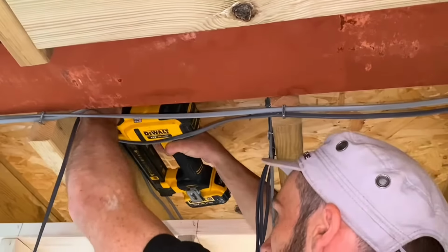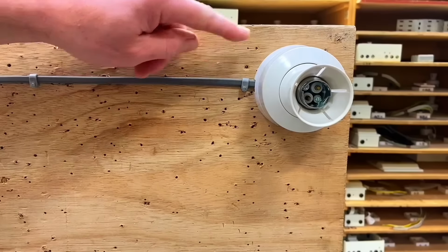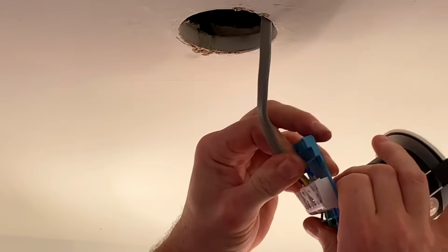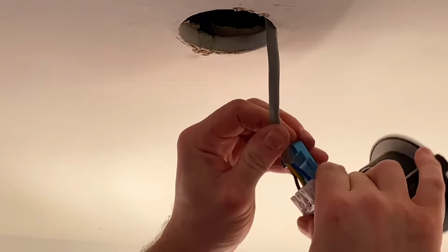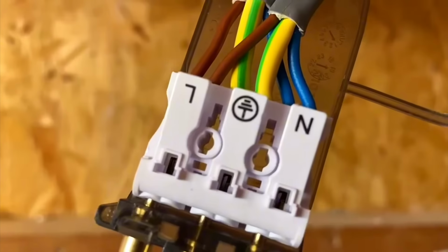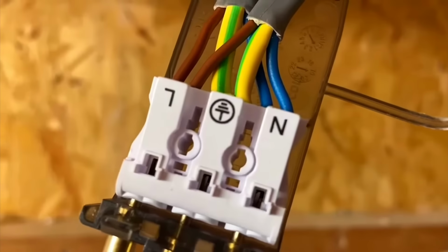With the evolution of many downlighters and spotlights in domestic dwellings, you're trying to reduce the number of cables at the light point itself. If we look at this circuit here, we've only got one cable entering this lighting point. If we were to have multiple points from the same switch, we'd come off here with another cable to other lighting points, meaning that you only have a maximum of 2 cables at any one, say, downlighter in an installation, making it easier to terminate for the electrician.